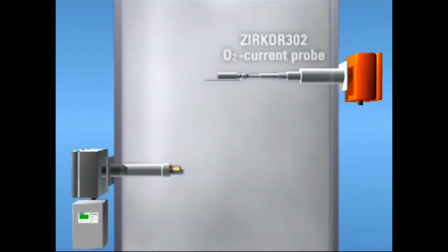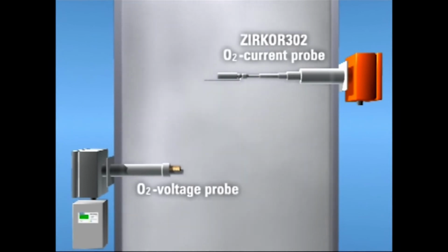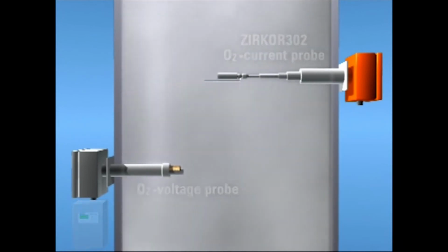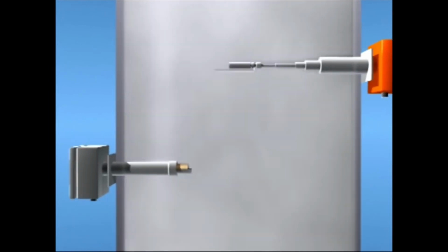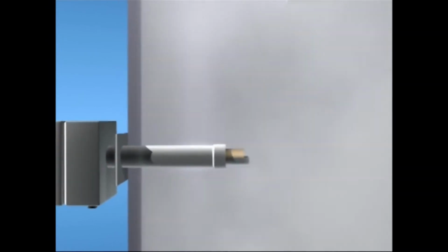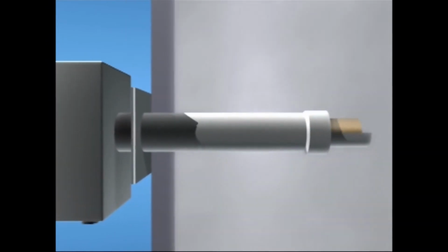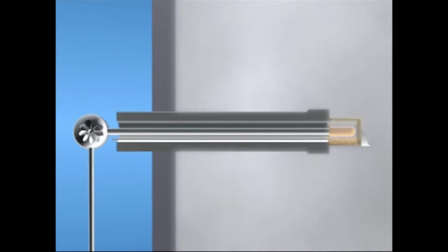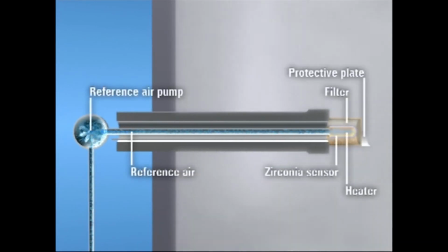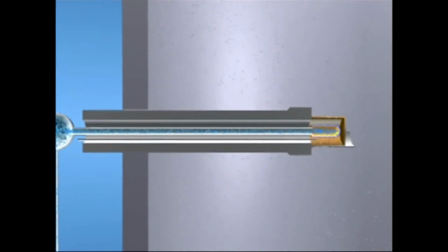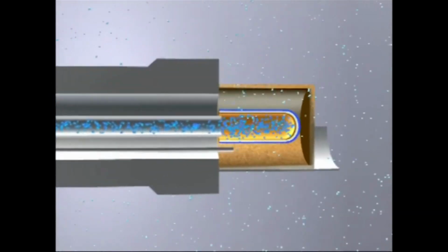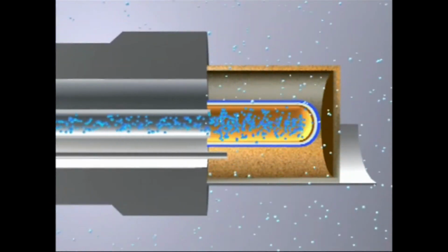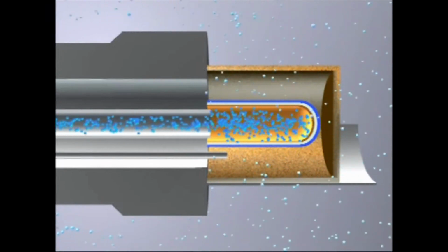We shall now compare two different technologies for measuring oxygen. One is the widely used voltage probe, the other is the ZIRKOR302, which is based on the zirconia current principle. The zirconia voltage probe works by diffusing the measuring gas through the filter onto a measurement electrode. The reference electrode, situated directly opposite the operational electrode, requires a constant supply of air containing 21% oxygen.